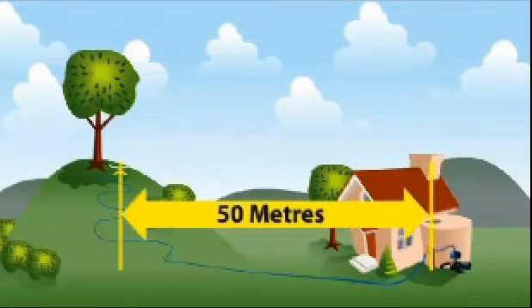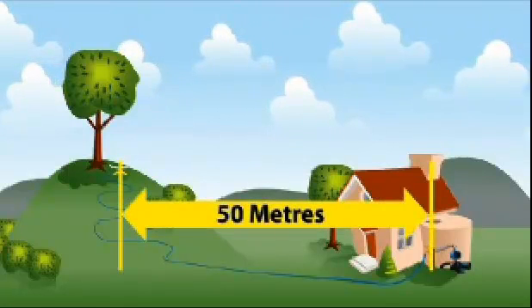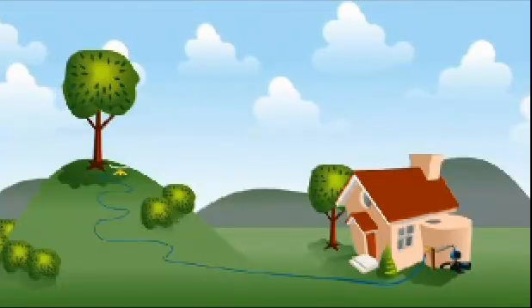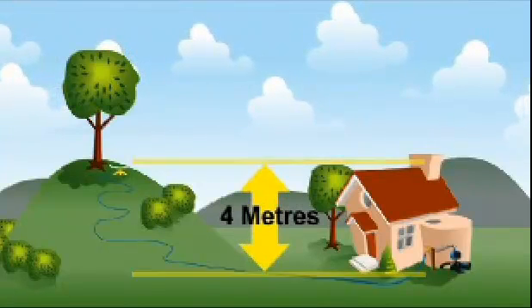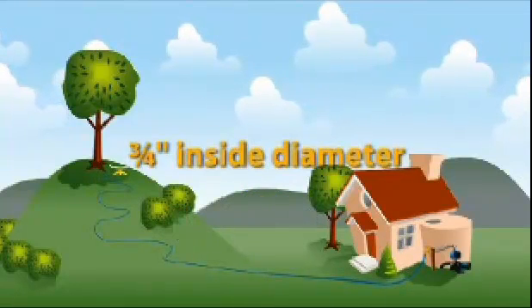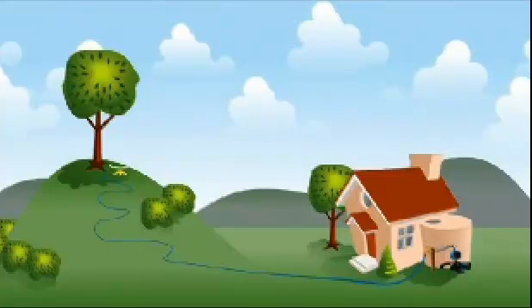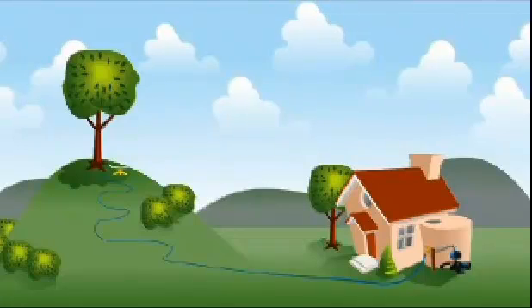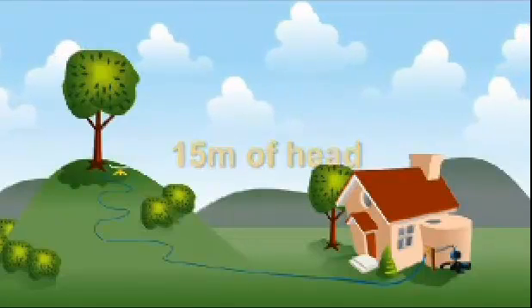From this point, she has 50 metres of pipework to the furthest sprinkler in her yard. This sprinkler is located at the top of the hill, which is 4 metres higher than the pump. The pipe she is using is 3 quarter inch in side diameter and she requires a flow rate of 45 litres per minute. The sprinkler has a demand pressure of 15 metres of head.